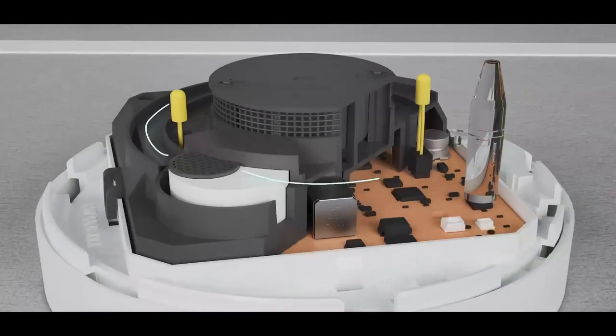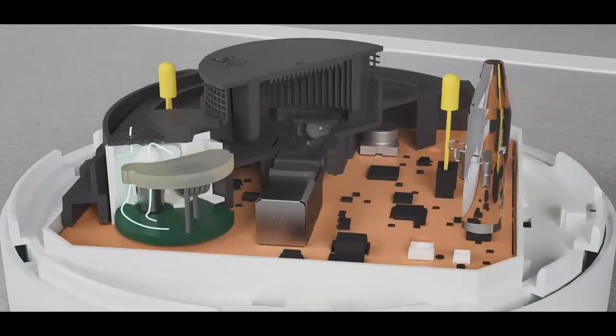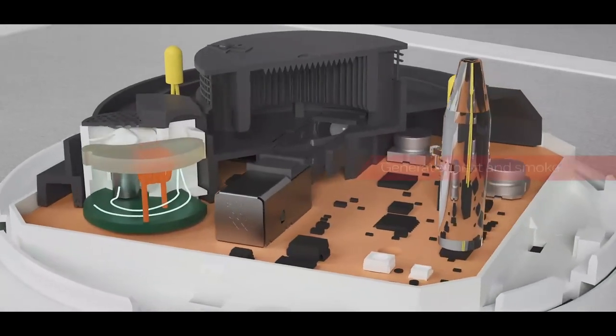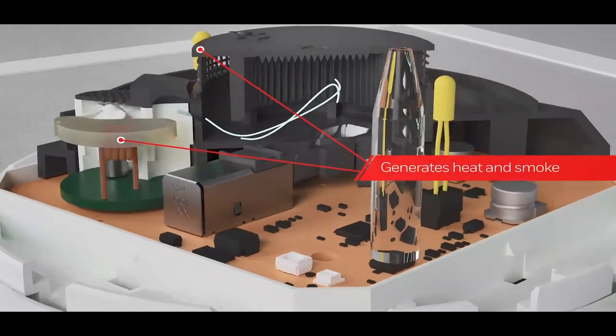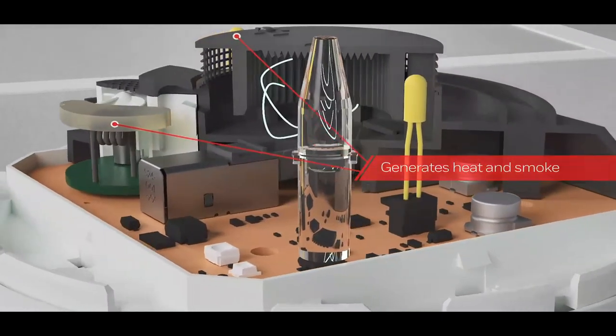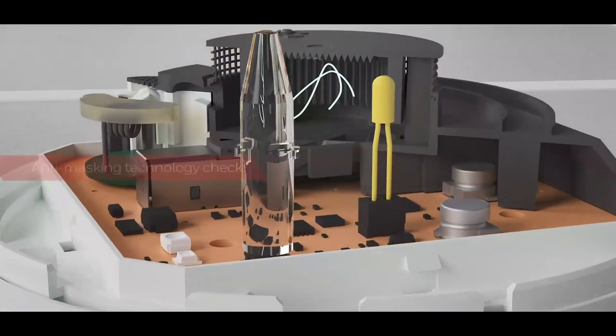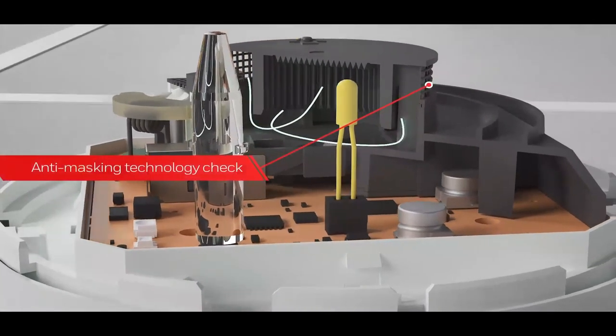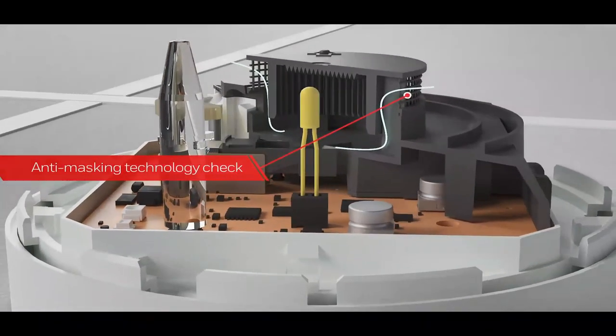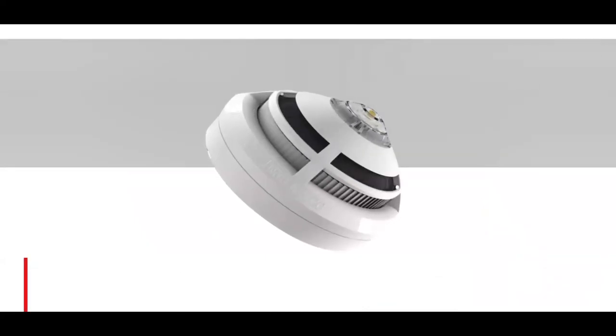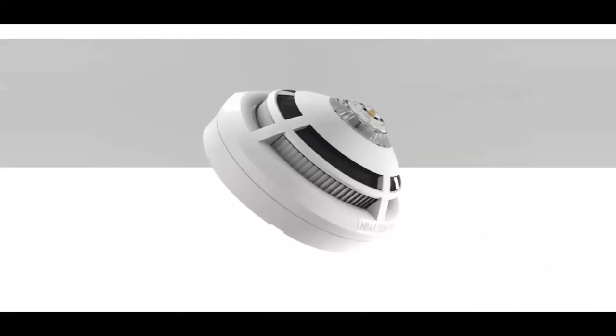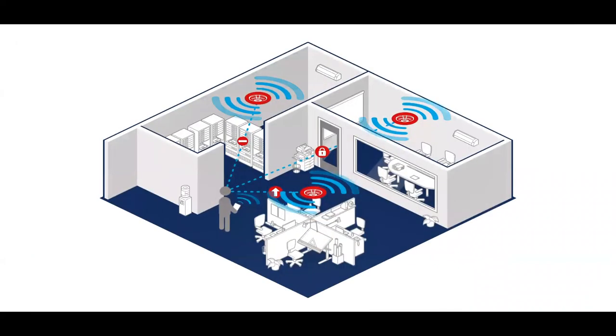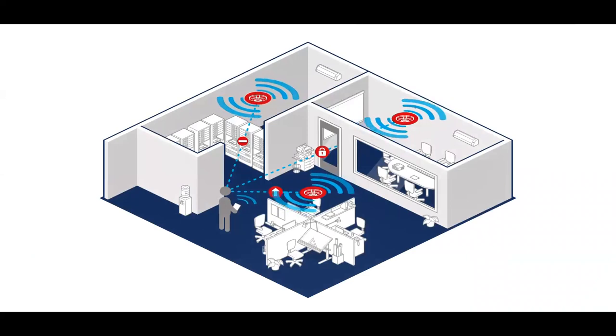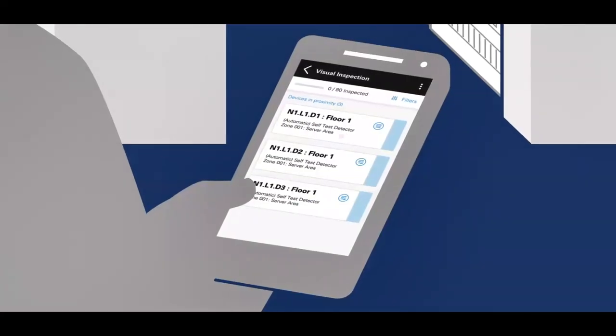This bit of video is showing how the thermistor checks itself. This is also how the smoke and the little fan whirring around. That's showing smoke going into the cell, so it's detecting it. It's also checking the smoke ingress and egress points to make sure it's not capped, so that you can see that it is actually working properly. That would normally be done by a guy with a pole. It does it on its own now, so you don't have to have somebody walking into those offices.